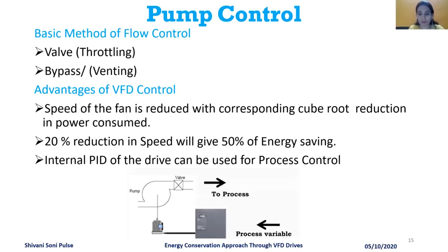So basically for fan and pump application areas: the ID and FD fans used in the power industry, HVAC systems, AHUs, cooling towers and blower systems, the fans are controlled by the VFD, and we get the maximum power savings there. In the same way in the pump area, there are service water pumps and chiller pumps. In pressure boosting and primary or secondary pumps, we use the VFD and reduce the power consumption of the motors.